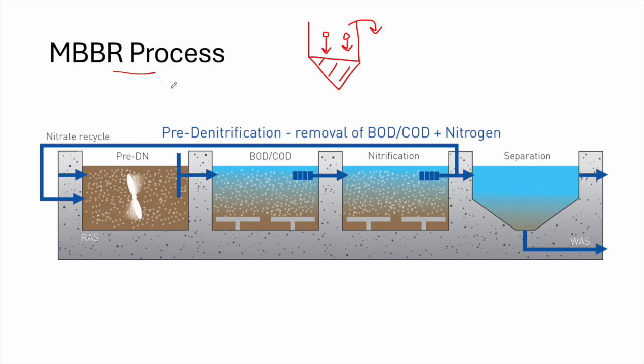After this mandatory primary treatment step, the wastewater undergoes secondary treatment — in this case, the MBBR process. We have several schemes for the MBBR depending on the desired effluent quality. Here we see a scheme capable of reducing nitrogen and highly removing BOD and COD, starting with a pre-denitrification or anoxic tank using anoxic conditions and a mixer.